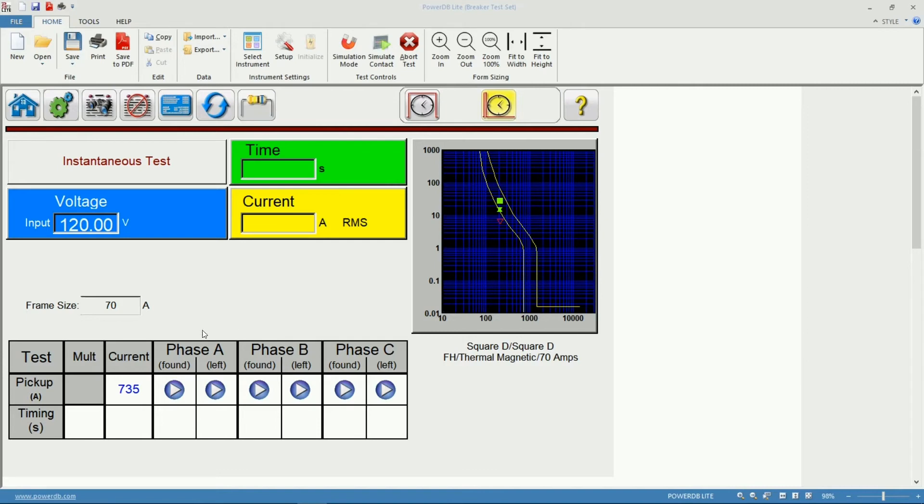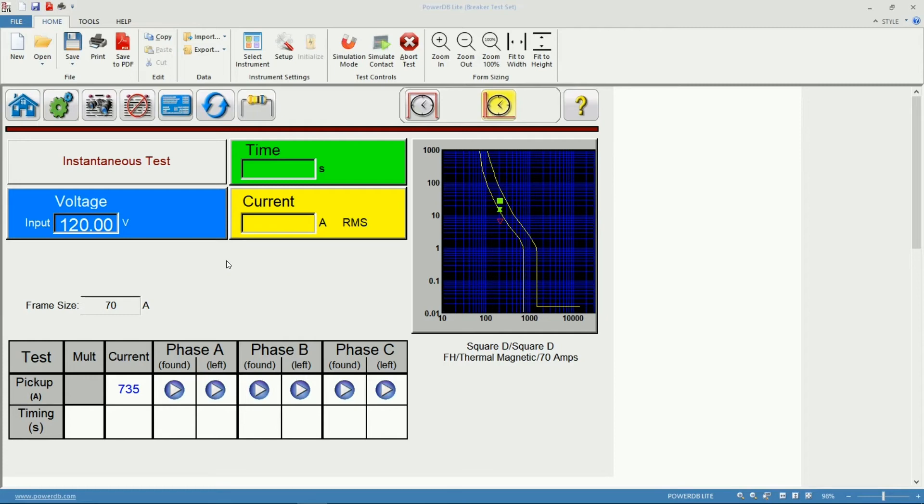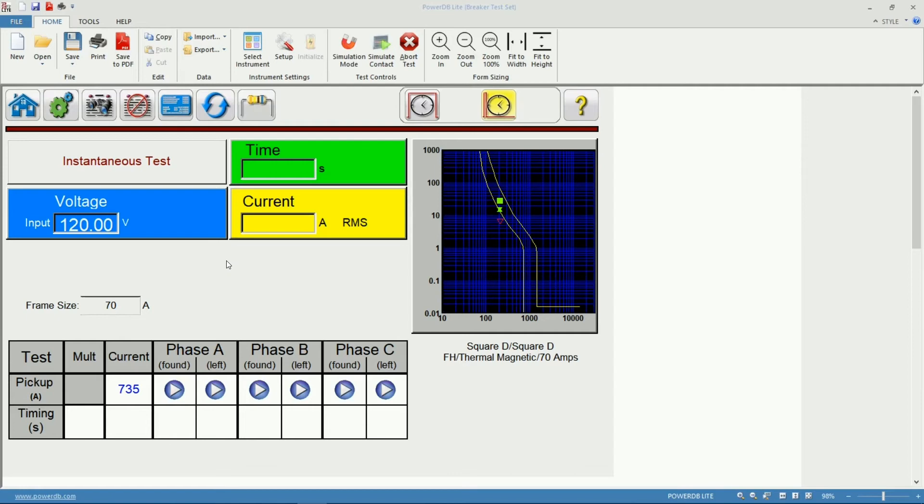But before we start the injection I want you to pay attention to the current meter in this section. Since the software will actually start the first injection in this case about 600 amps, in case the breaker is tripping below the expected limit we don't want to miss that value. The purpose of this test is to determine the instantaneous pickup so we want to know the lowest possible value at which the circuit breaker will trip in that function. Pay attention to the live current indicator up here in yellow.